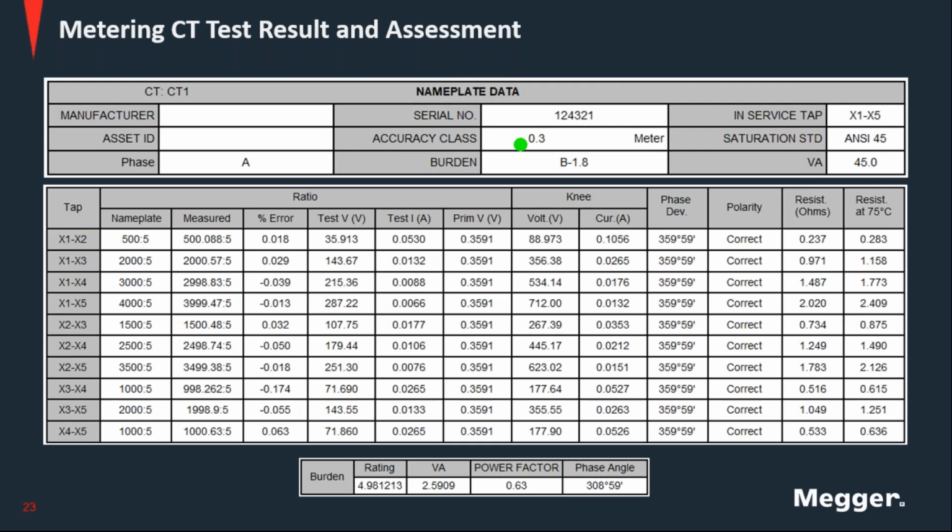According to this accuracy class, we could have plus or minus 0.3% here, so we are far from that, meaning the ratio is very good. And we can start picturing this in a parallelogram, and we know it's going to be pretty much in the center of that parallelogram, at least in what relates to the y-axis. Oops, sorry, I pressed the wrong one.